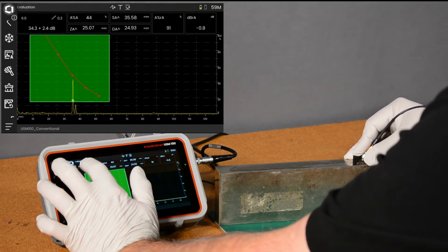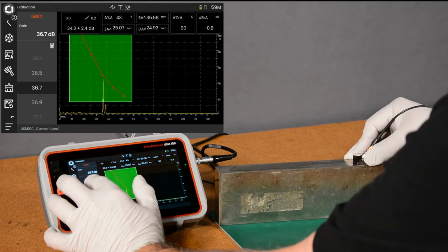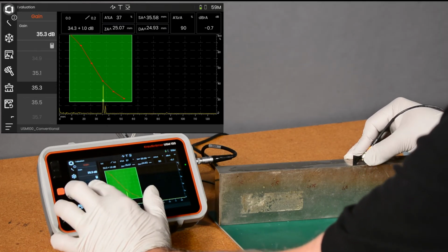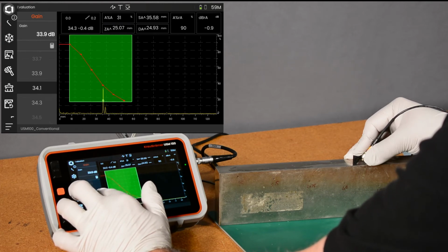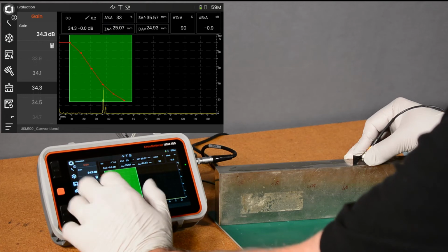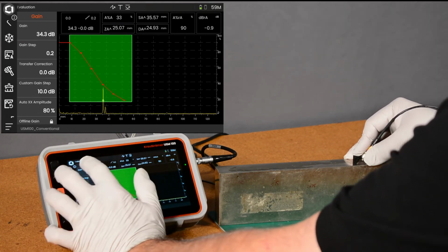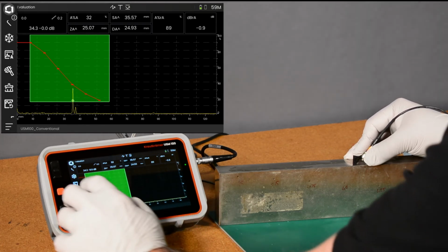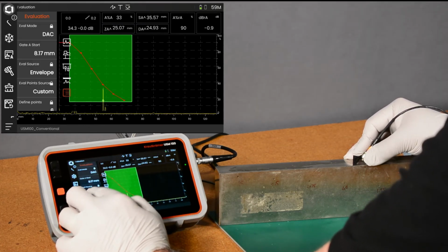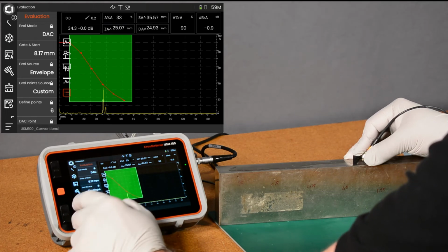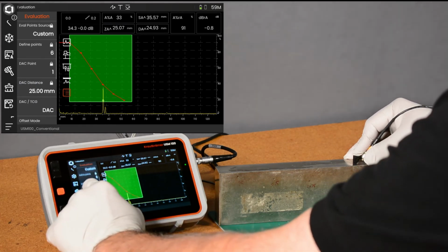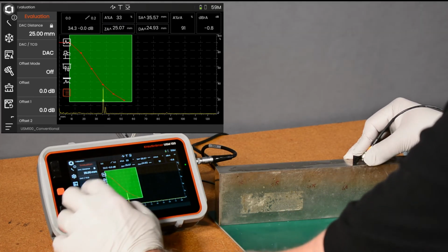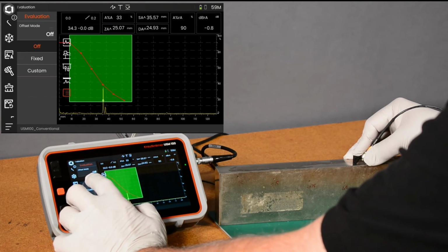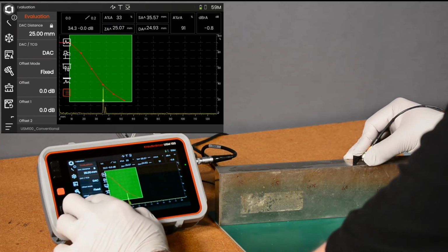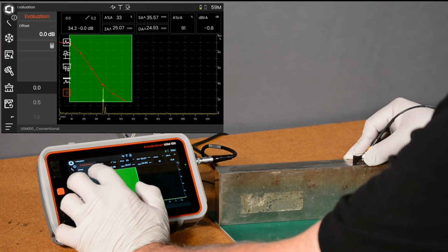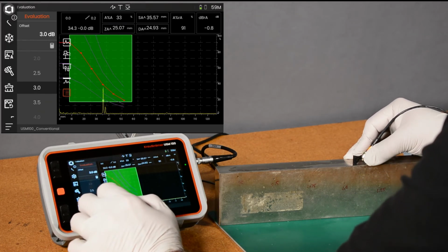So we're back to nearly the same gain that we had before. Let's come in here and we will come down a little bit. We'll get back to our calibration gain. So now we're back to our 34.3 with no gain offset. Okay, so now we see our same curve. Now, if we come in here and go to the evaluation menu, we scroll down here a little bit, we can get some offset curves. So let's take our offset and we'll tell it we want fixed offset, and we want an offset of, say, 3 dB between our parallel curves.